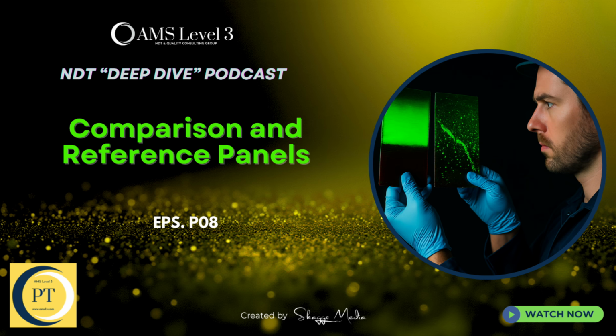Enter the fractured glass step wedge panels. Right. These are pretty neat because they let us move beyond just looking at brightness to getting actual numbers. They're made of special glass. It's transparent to the UV inspection light, but opaque to visible light. This means you can see the penetrant trapped in the cracks from underneath and measure its brightness directly.